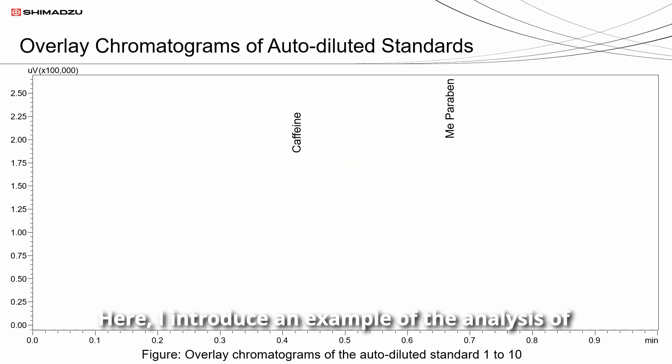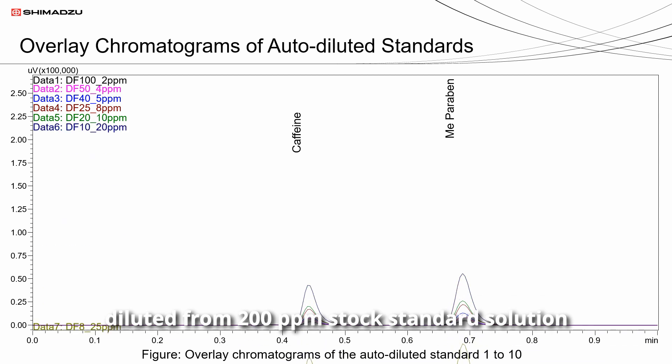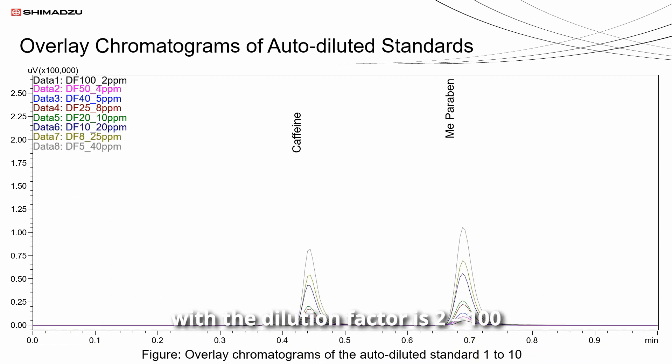Here I introduce an example of the analysis of caffeine and methylparaben using the auto dilution pre-treatment function. The figure shows the overlay chromatogram of the auto-diluted standards 1 to 10, diluted from 200 ppm stock standard solution with the dilution factor of 2 to 100.